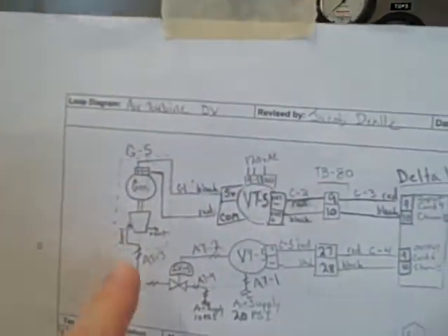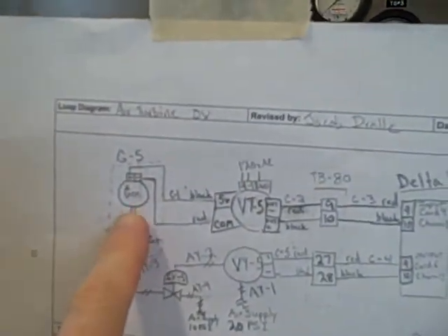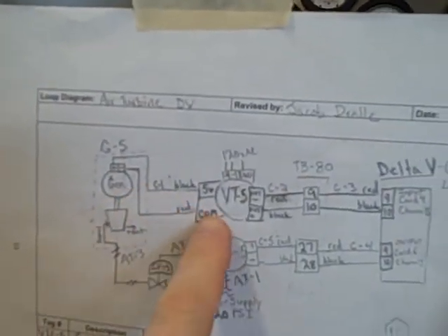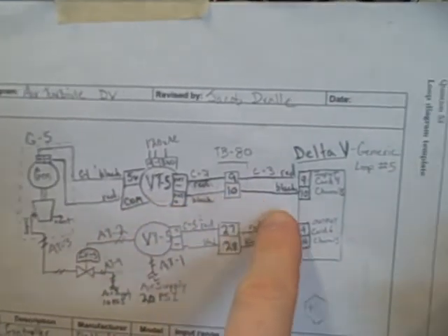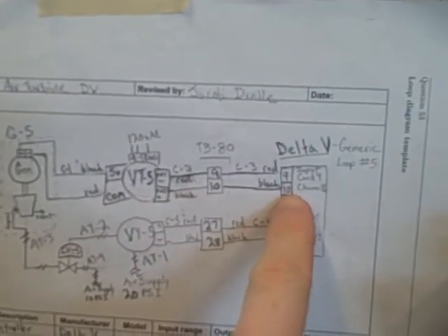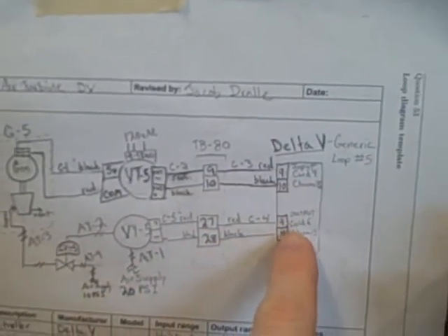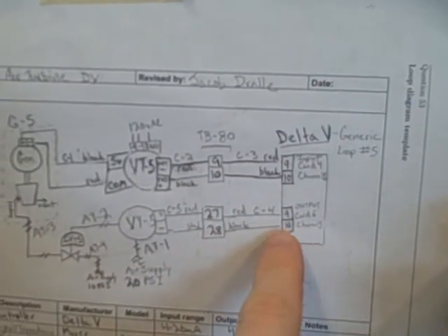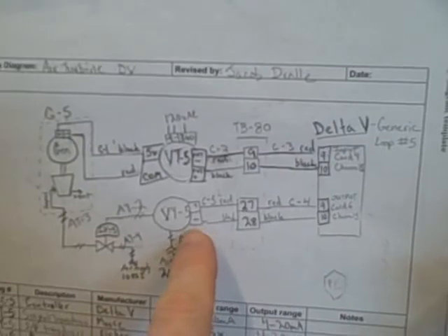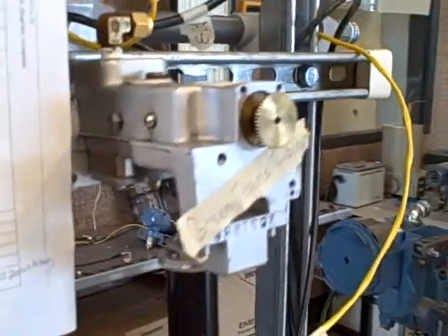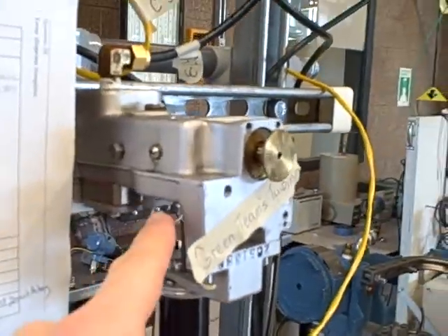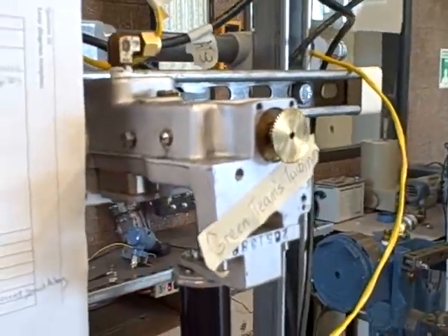We actually take the generator signal right here in the loop diagram, pass it through a voltage-to-current converter into our Delta-V DCS. The DCS then generates the signal out to our valve, our I to P, and out to our valve, sending variable amounts of air to rush through the turbine.